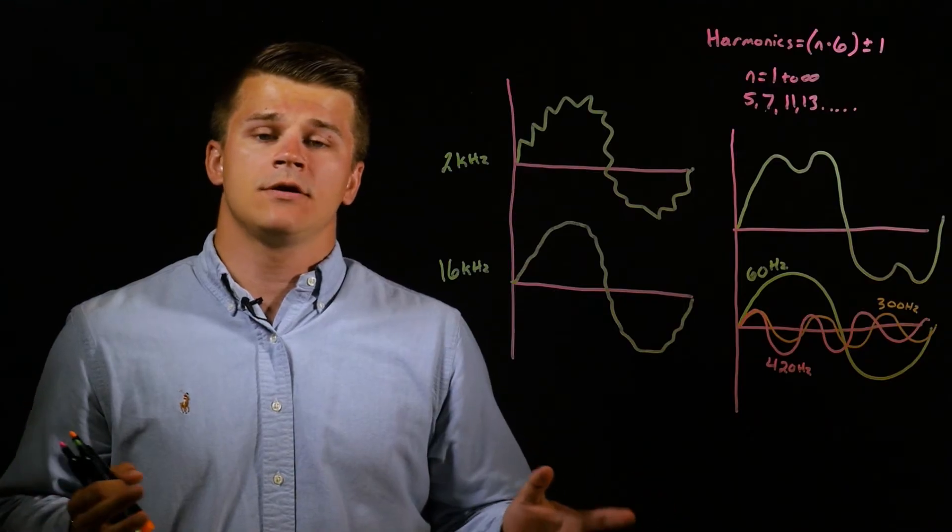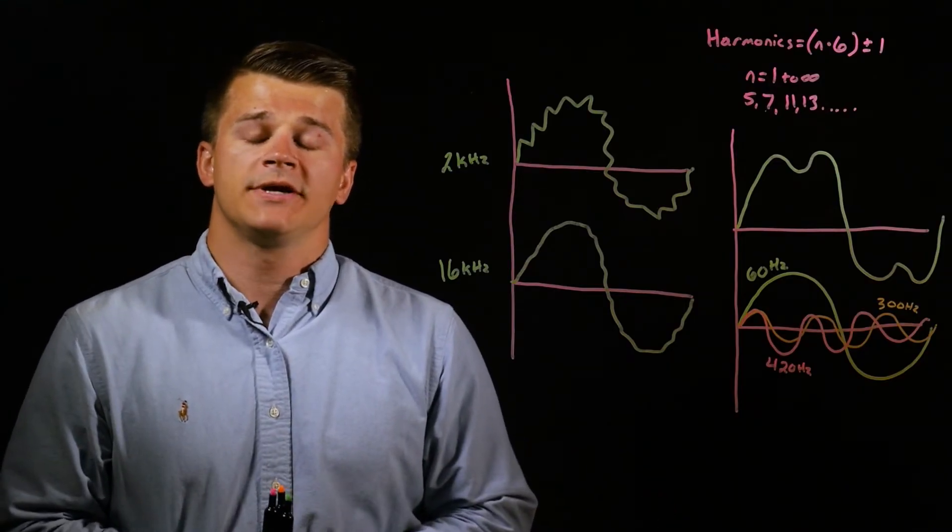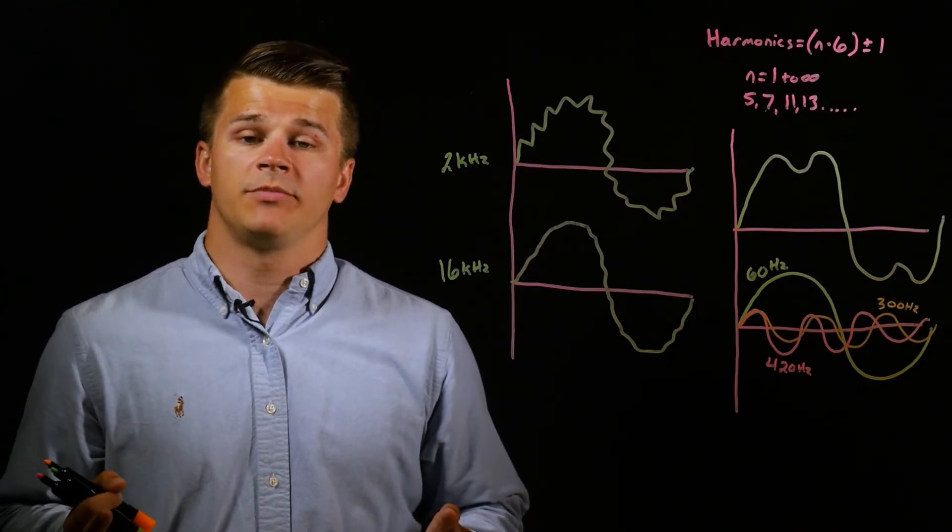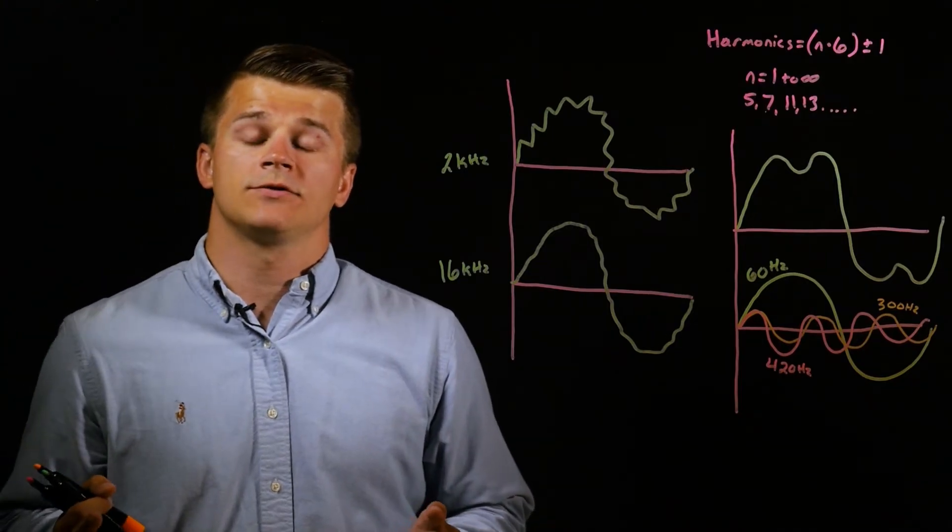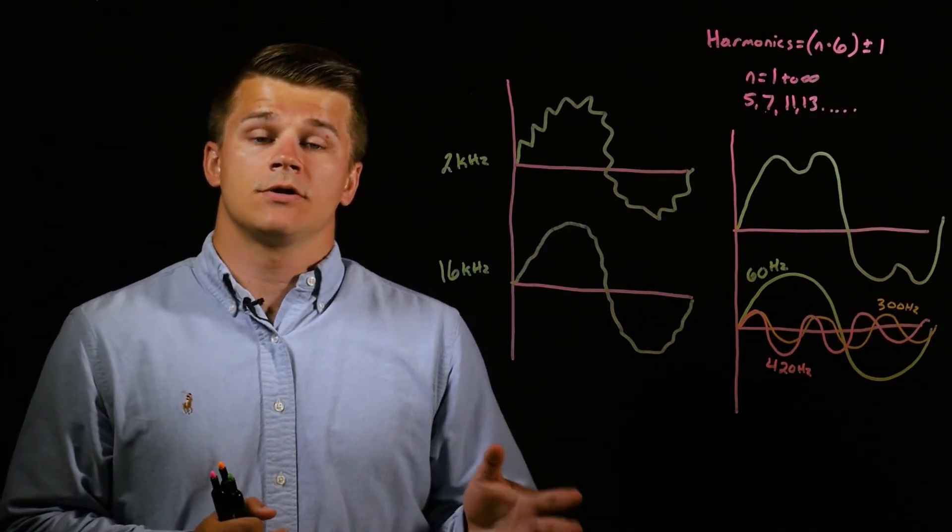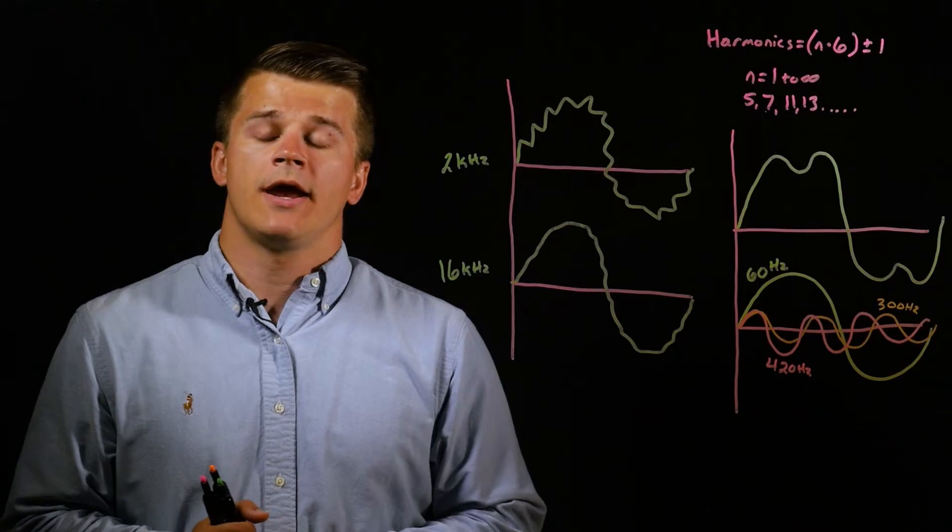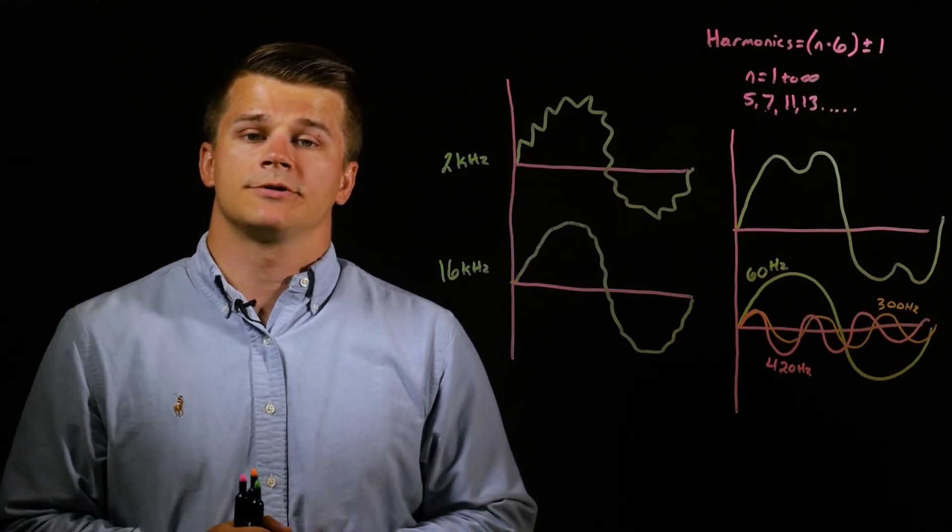There are some downsides to increasing the switching frequency. The biggest is that it increases heating in the drive because the IGBTs are switching on and off so rapidly. It can also increase EMI noise in the system and cause you to derate the output current to the motor.